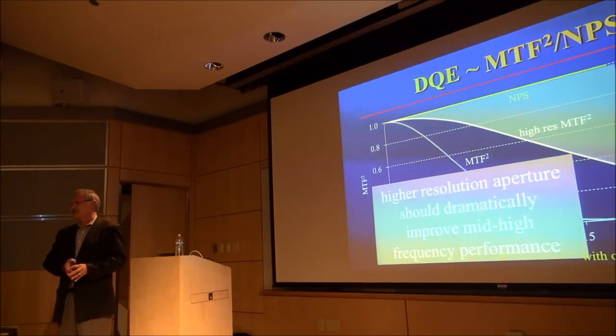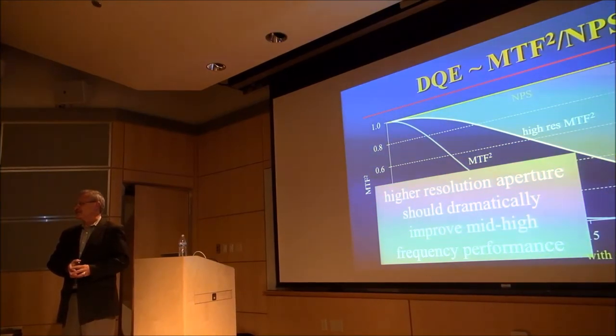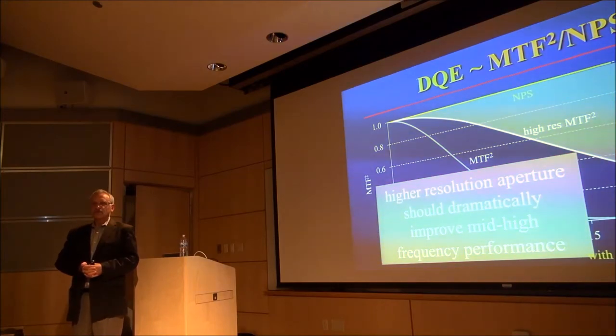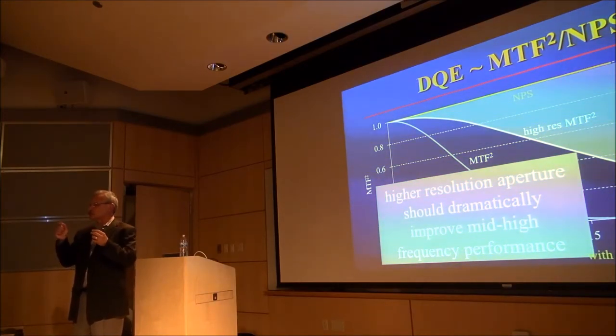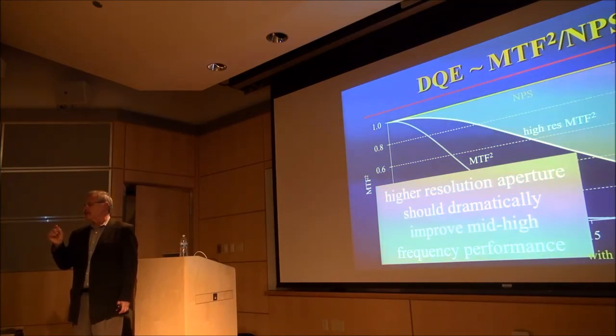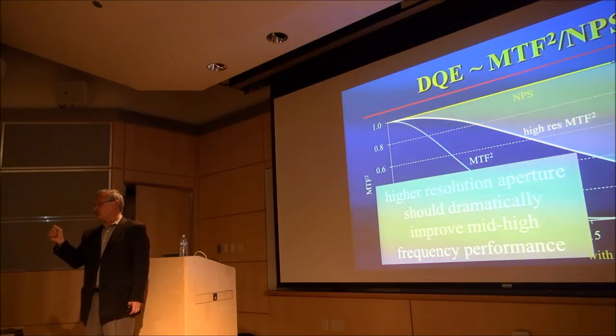Is there going to be any problem as we go faster in rotation speed with respect to the focal spot itself? Are these going to be cold cathode emitters or standard filament type thermal? I don't think there are problems with distortion of the shape of the focal spot. There's a new Siemens tube that I believe is a cold cathode emitter, like a dispenser cathode. I think we probably will see abandonment to some extent of thermionic emitters, but I don't think that's essential. Although I will say that Siemens claims for the same power, they get better resolution because they have a more uniform focal spot with these cold cathodes.